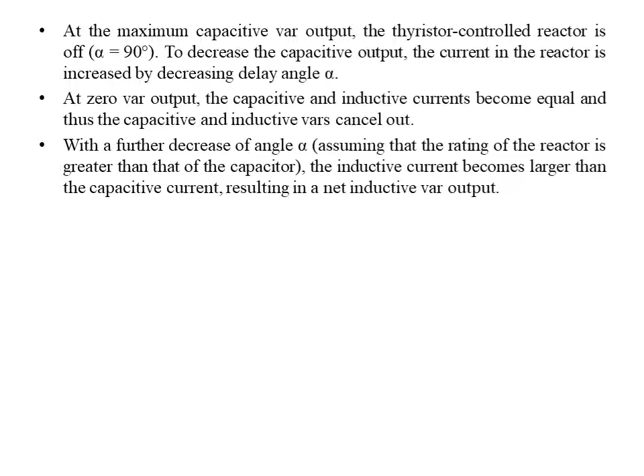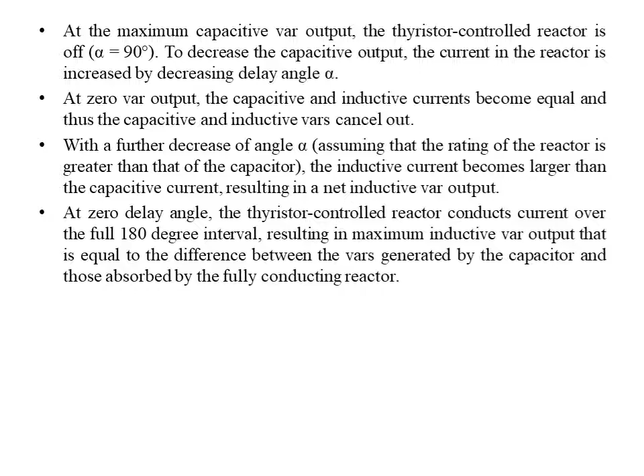At zero delay angle, that is, when alpha is equal to 0, the thyristor controlled reactor conducts current over the full 180-degree interval, resulting in maximum inductive VAR output, that is equal to the difference between the VARs generated by the capacitor and those absorbed by the fully conducting reactor.